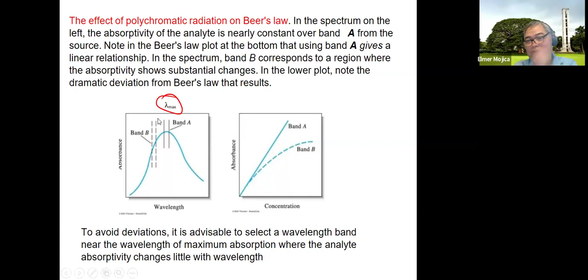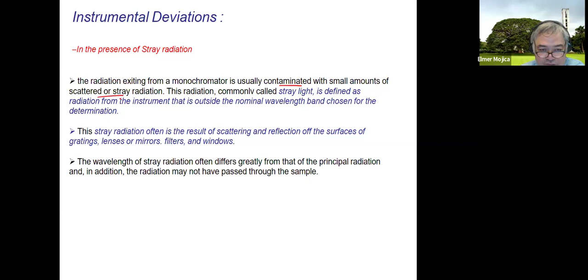Now, the other one that we have is stray radiation. So usually the radiation that exits from the monochromator is contaminated with small amounts of scattered or stray radiation. This radiation, which is known as stray light, we define as radiation from the instrument that is outside the nominal wavelength band chosen for the determination.